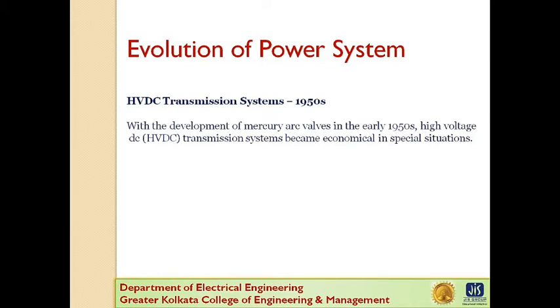specific situations. HVDC transmission is attractive for transmission of large blocks of power over long distances. The crossover point beyond which DC transmission may become a competitive alternative to AC transmission is around 500 km for overhead lines and 50 km for underground or submarine cables. HVDC transmission also provides an asynchronous link between systems where AC interconnection would be impractical because of system stability considerations or because the nominal frequencies of the systems are different.